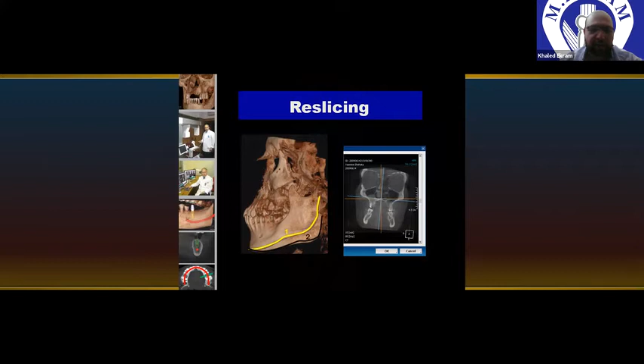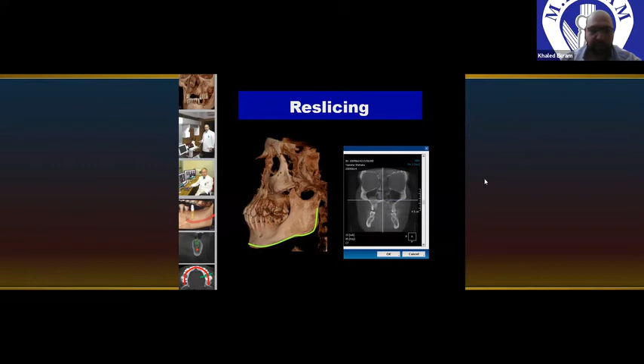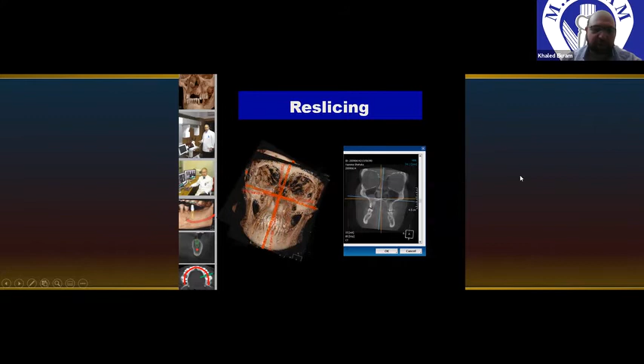For example, correction of the head position or the occlusal plane. In CBCT, if the patient was scanned from the beginning of the scan maneuver until the end with a tilted head, the software can then correct this error and reform or reslice new cuts, which are made as if the patient was placed correctly in the machine. Here also, if the patient's head was tilted, the software can correct it and then reform the required slices.